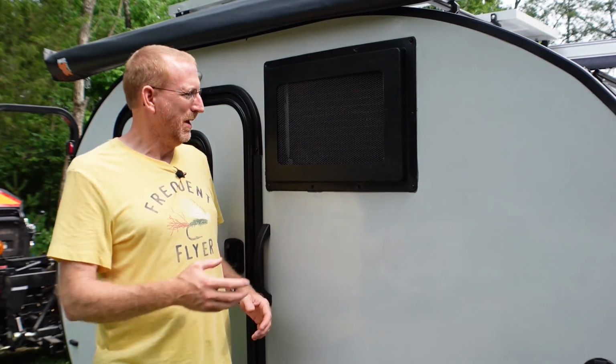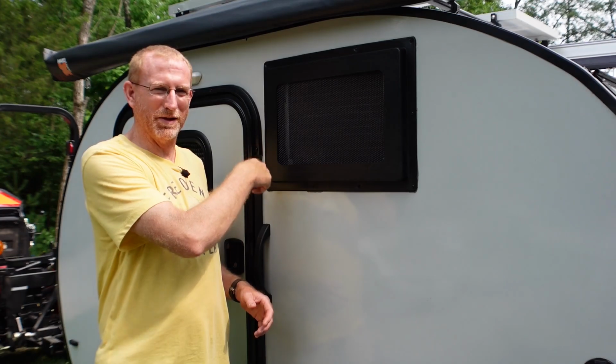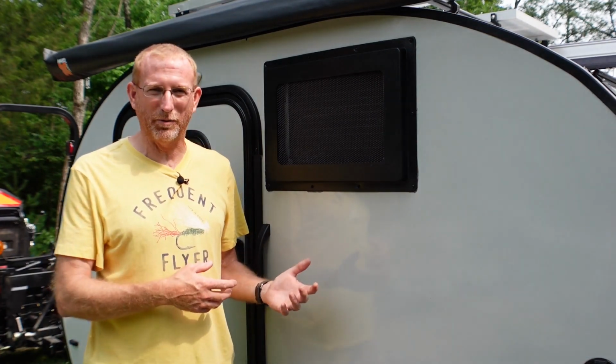And there's a great safety concern. This unit actually plugs in right inside this cabinet and the plug-in is open to the air conditioner. So the way I see it, you're slinging water right at the backside of that outlet. You don't want to mix electricity and water, which is exactly what they're doing. We're going to fix that tomorrow when we take this out.